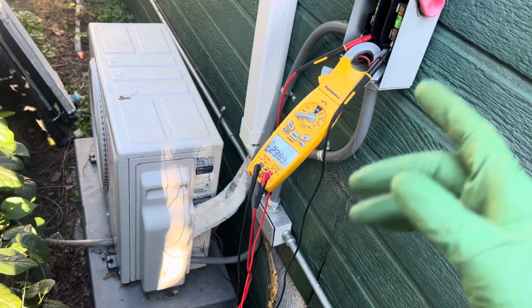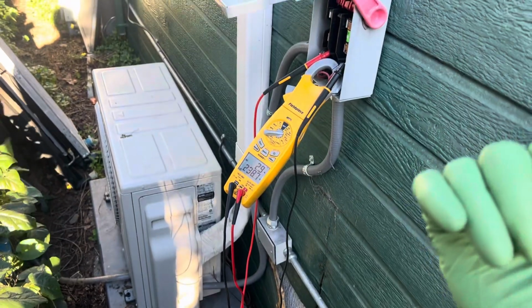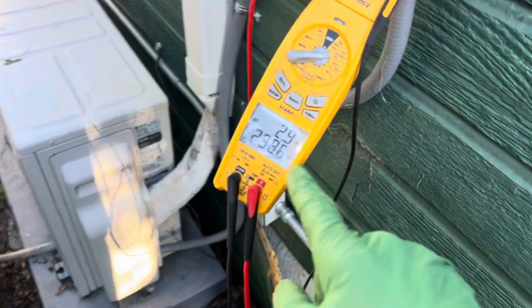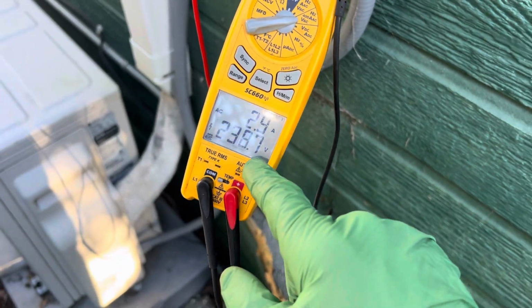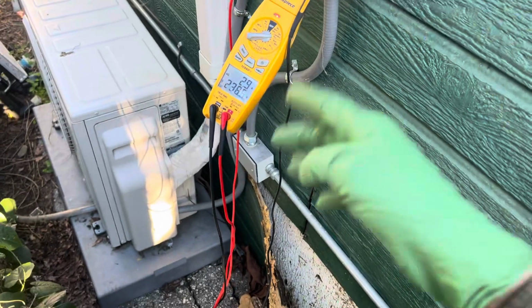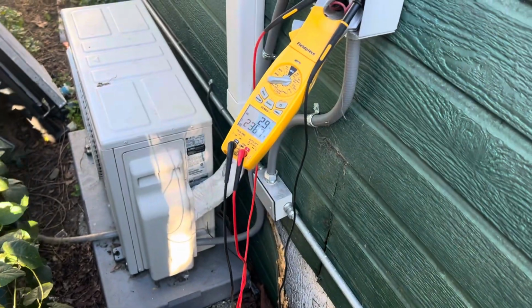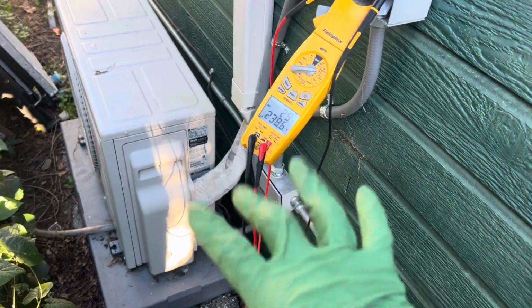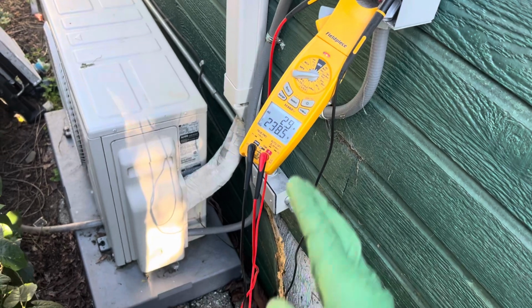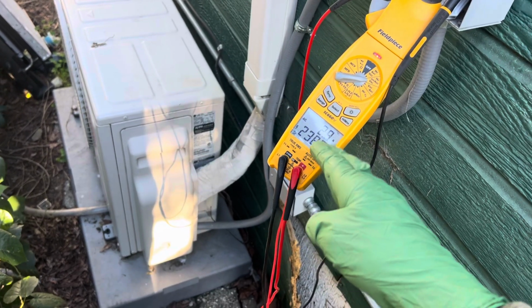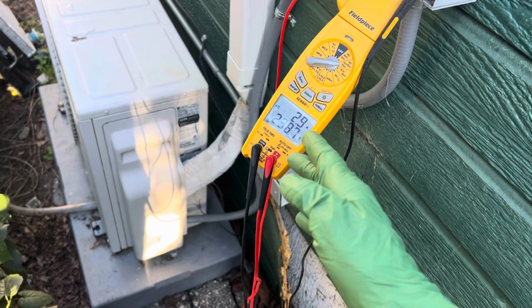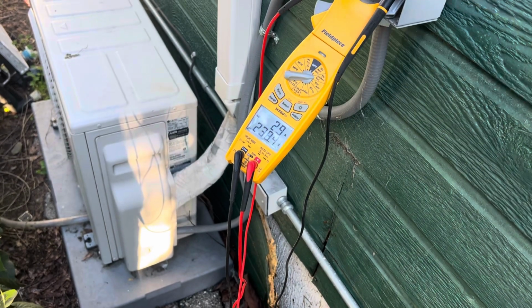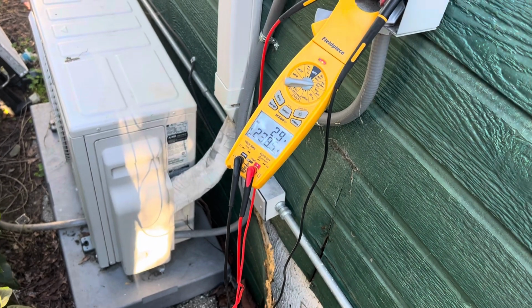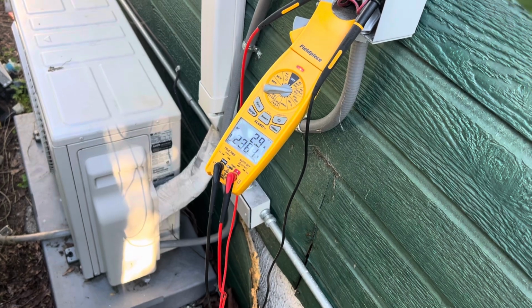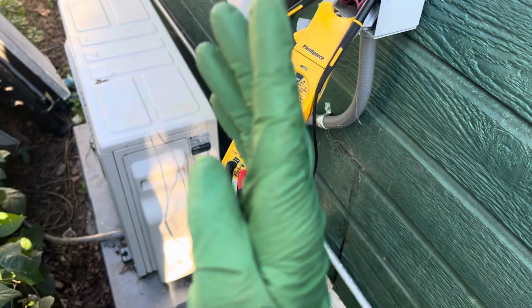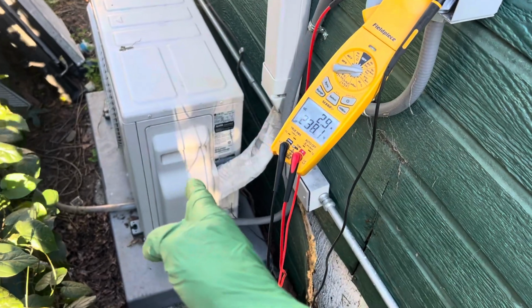So we had a blown circuit breaker on the indoor main panel. We're reading almost our 240 volts here, 236. Less is best, you don't want more volts, fewer volts is better. Some areas of the country, the power supply company boosts the voltage really high, over 250 volts, like 253 volts. You're getting to the point where you can actually cause damage to the power inverter boards.